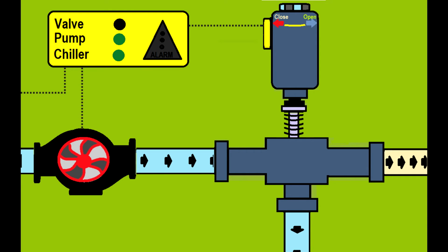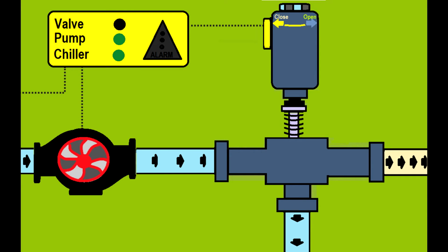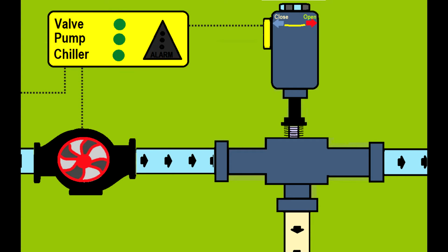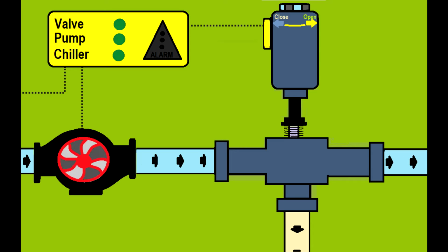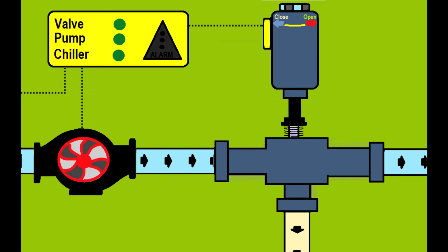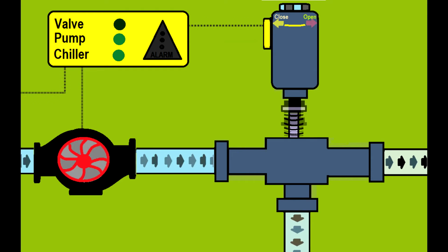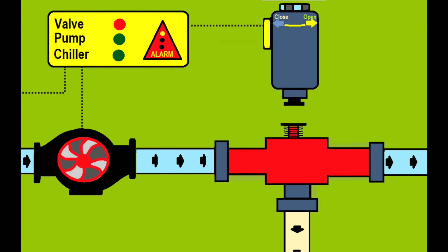Now if the pump runs, you will see this is a 3-way valve. When the valve is closed, you divert the heating agent or cooling agent. In this situation, the valve just opens and allows the cooling agent, in this case, to reach the heat exchanger. In this case, it starts to control its capacity, returning only a portion of the glycol.